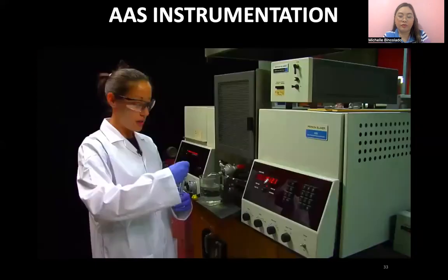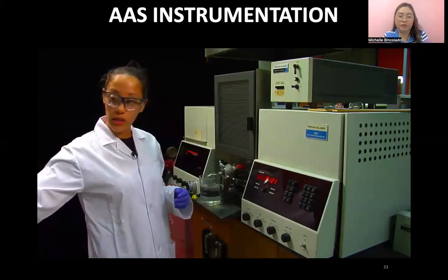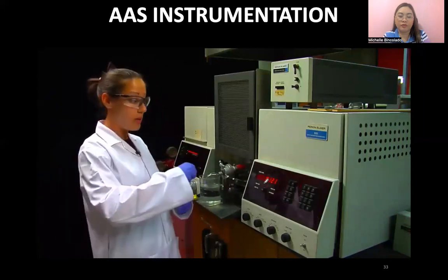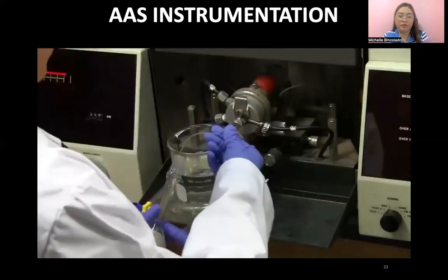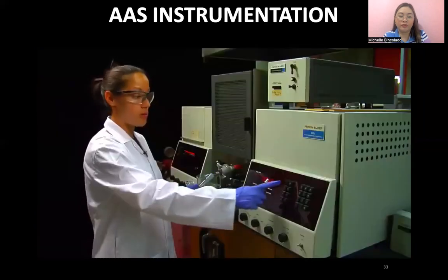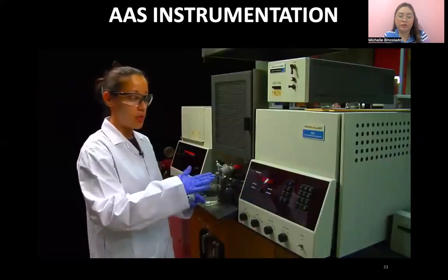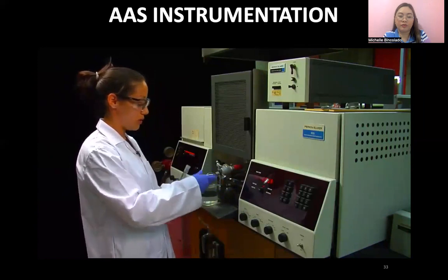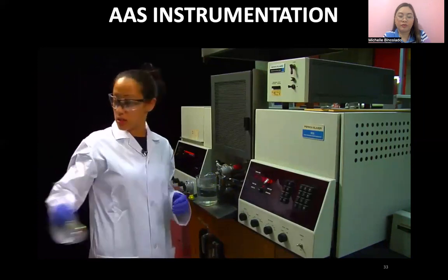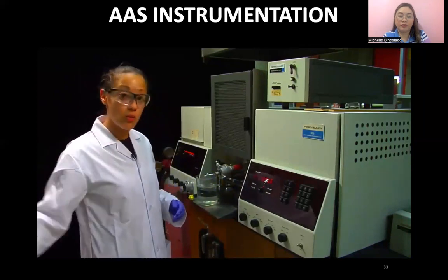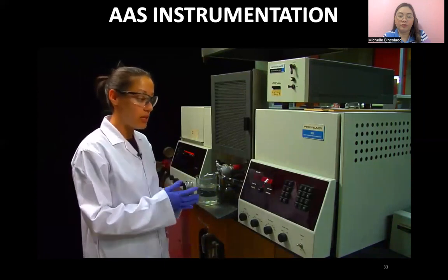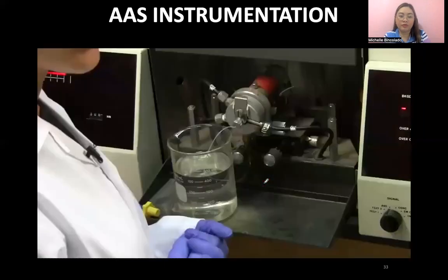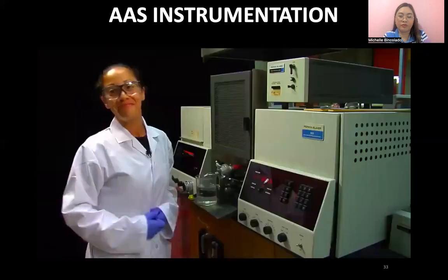If you find your numbers fluctuating a lot, feel free to, at any time, take your 0 and zero the machine, just to make sure your background is relatively the same for all your standard readings. Then you continue with the rest of your standards, and now you have enough data to build a calibration curve and measure your unknown.